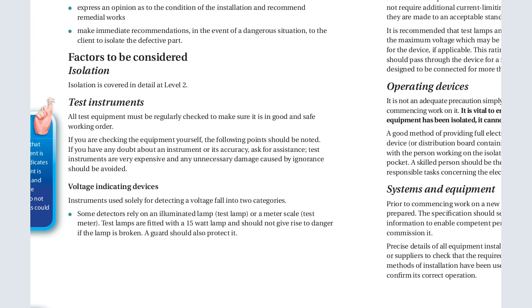Another thing that has to be factored in is the voltage indicating devices. These are instruments used solely to detect voltage and fall into two categories. That is, those detectors rely on the illuminated lamp test and the meter scale test. So the meter test lamp is fitted with a 15-watt lamp and should not give rise to danger if the lamp is broken. That is, the guard should also protect it.